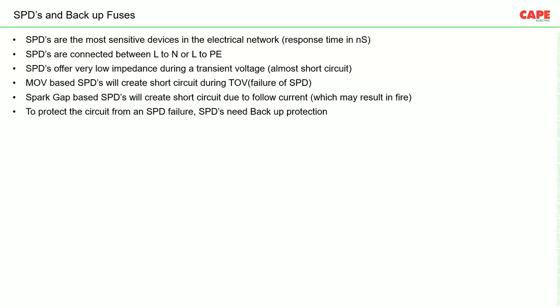MOV-based SPDs will create a short circuit during TOV. A normal SPD may have a maximum continuous operating withstand capability of, say, 300 V. If it experiences a temporary overvoltage of 440 V — due to neutral cut or similar — and this condition is prolonged, the SPD can fail and create a short circuit. In sparkgap-based SPDs, a short circuit can also be created due to follow current, which can result in fire.